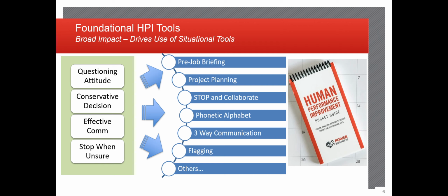Three-way communication, that is another thing that we utilize, especially during the isolation procedure. Somebody will be holding the prints, communicating to someone at the piece of equipment. They're going to relay that information. The person at the piece of equipment is going to relay it back to understand that they heard everything correctly and repeat it. And the person back on the prints will either say, yes, that's correct, or no, and go over it again.